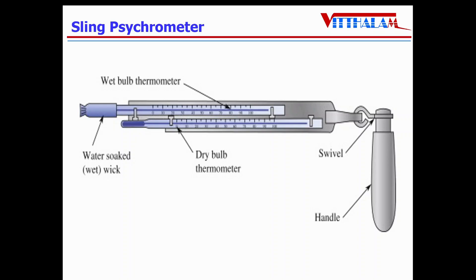When the sling psychrometer is spun rapidly in the air, the water from the wick evaporates and draws heat from the thermometer, which causes the wet bulb thermometer to read lower than the dry bulb thermometer. After the psychrometer has been spun long enough so that the thermometers reach equilibrium temperatures, the device is stopped and the readings are quickly noted. These two thermometers measure the dry bulb temperature and wet bulb temperature of the air.